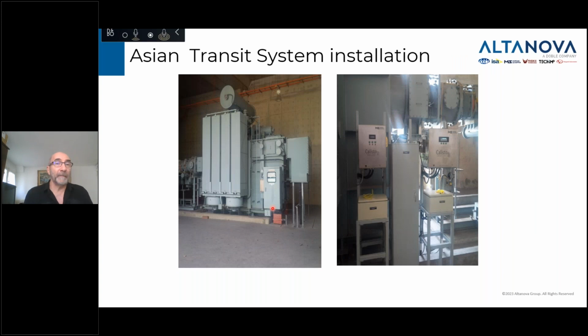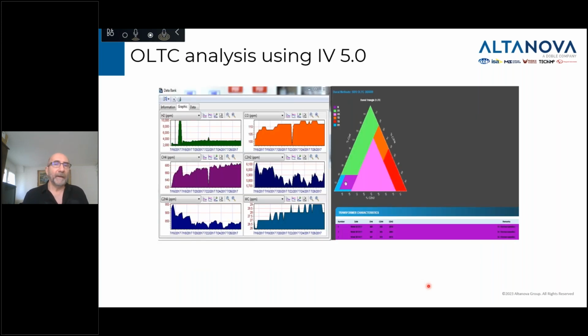Here, this is a transit system installation in Asia on a 75 MVA transformer. What they've done is measure multi-gas on the OLTC, and they're measuring dual gas in the main tank as an alarm system. And what they're doing on a regular basis is taking the data from that OLTC and automatically putting it into a diagnostics system using the Duval OLTC triangle. It's the same example I showed earlier. So what you can do with that system is really see if there's any deterioration in that OLTC that will tell you that at that point, the customer has to do some kind of maintenance on that OLTC.